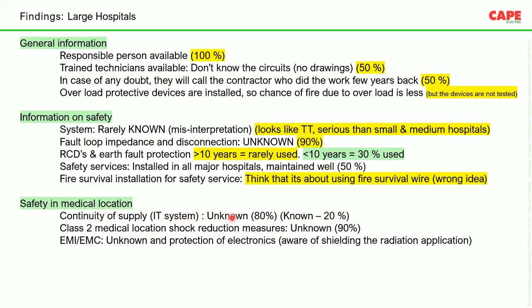Safety in medical locations, continuity of IT supply: mostly it's unknown, 80%, and about 20% it is known. Class 2 medical location shock reduction measures are again unknown in 90% of cases. The shock reduction supplementary protective equipotential bonding is missing. In some hospitals, of course, rubber flooring is made, thinking that this may protect from shock. But in a conductive location, where conductive fluids are sometimes on the floor, it will be very difficult to achieve safety that way. Of course, rubber or plastic flooring is required, but protective equipotential bonding is also required. You cannot avoid it.